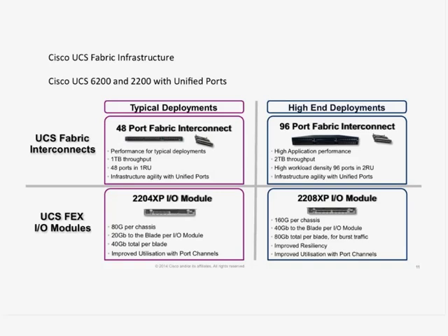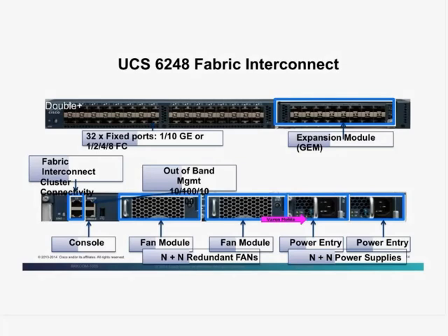One more requirement that I wanted to let you know is that Ethernet ports are always configured from left to right, whereas the FC ports are configured from right to left. And the port numbering always starts from an odd number, so you can end your Ethernet ports out here. If it ends here, the first FC port would start here. So you need to be very careful during the port assignment.